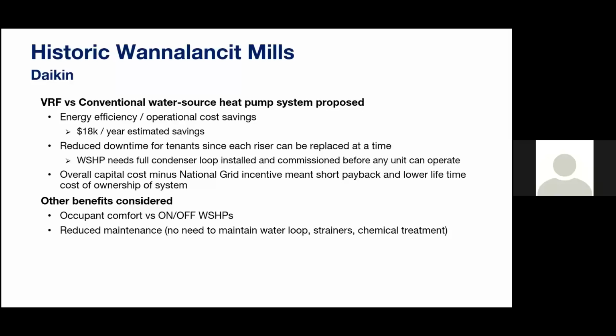We've also actually had the maintenance staff all trained up on the VRF systems, and even had one of the VRF central controllers, which we touched on, installed, which allows them to remote access into the system and then do any sorts of things like programming for schedules or set points, and also helping with diagnosing issues. And then, as I mentioned, the owner was pretty happy with the solution, and we've even gone forward with another 30 units in other parts of the building.